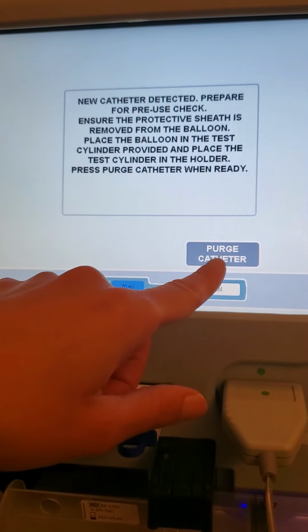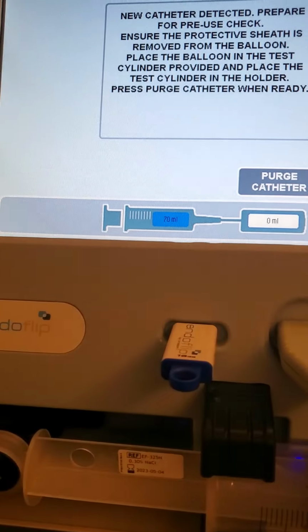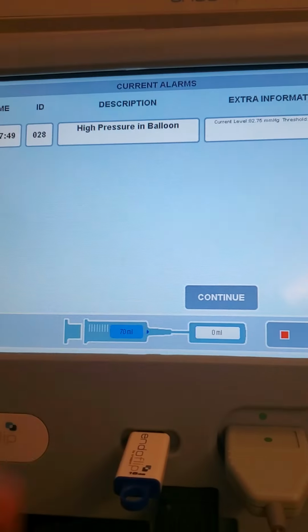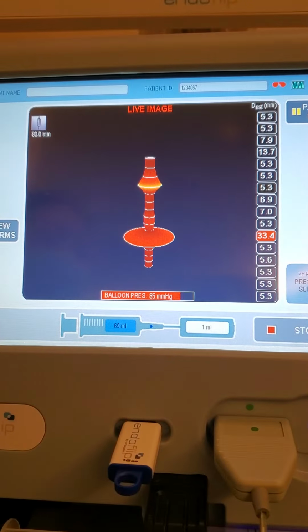Make sure that everything is connected, and then press purge catheter. So I like to just do one more check: locked, connected. This is in with no sheath, we're good to go. Now I go ahead and press purge catheter. If you get that high pressure warning, just press continue.